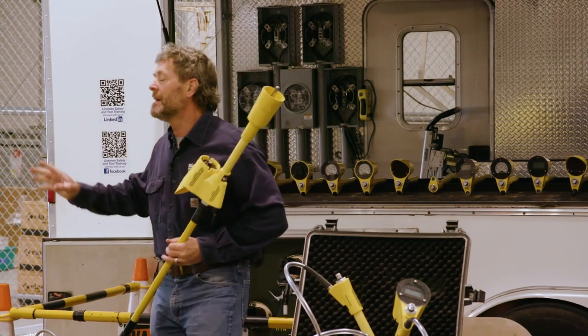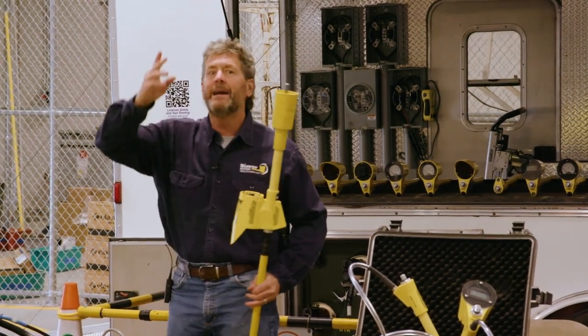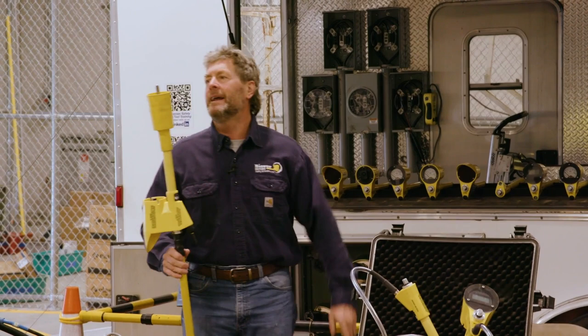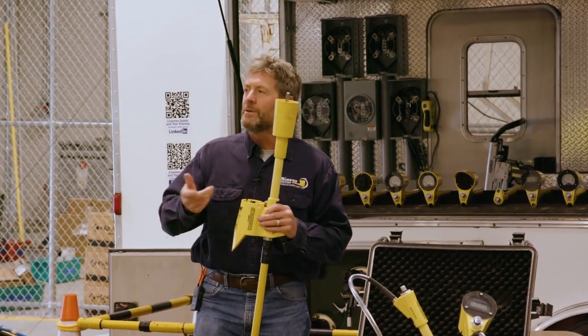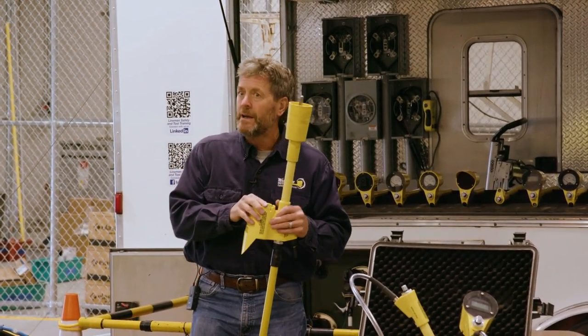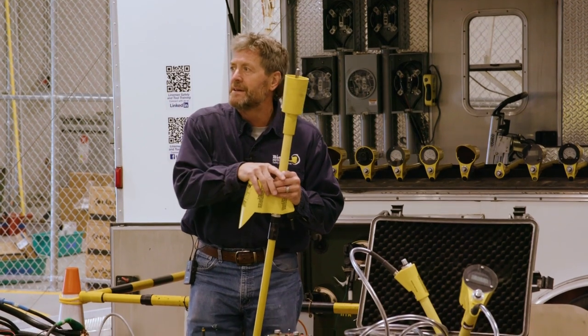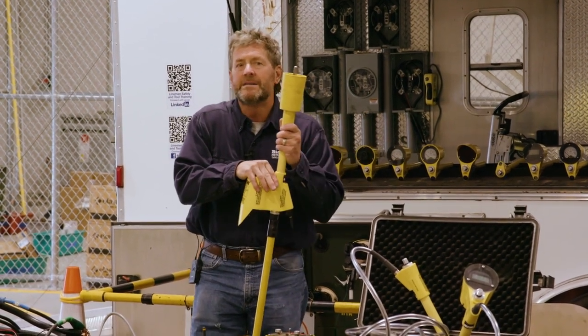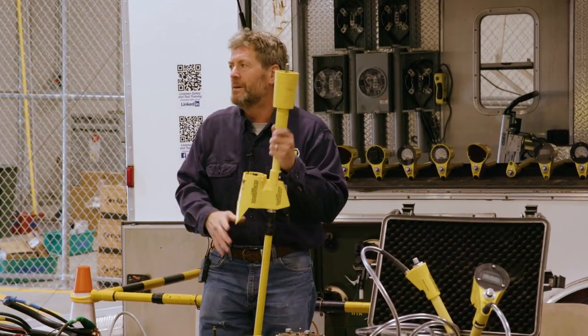You touch any conductor, any height, any span, any dimension, any name, any title, and you get a blue light 120 or close to 120, that's going to be your B phase. Red light 240, C phase. It's real simple, and it's that fast too.